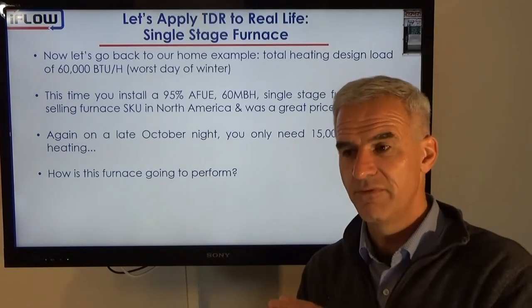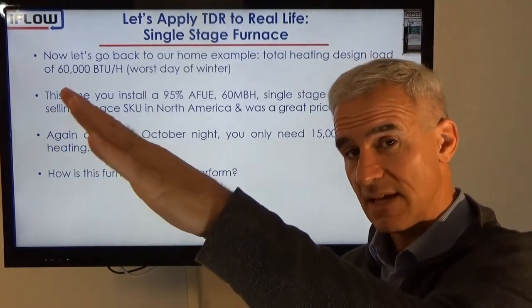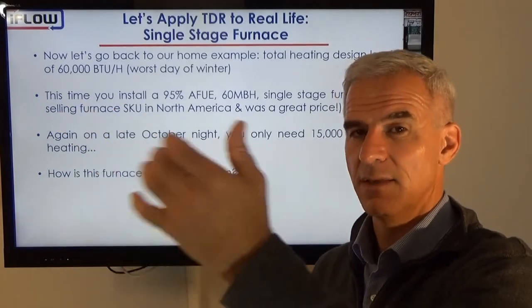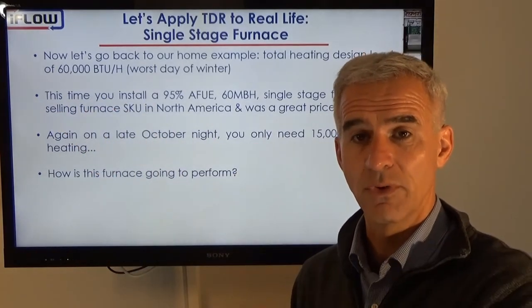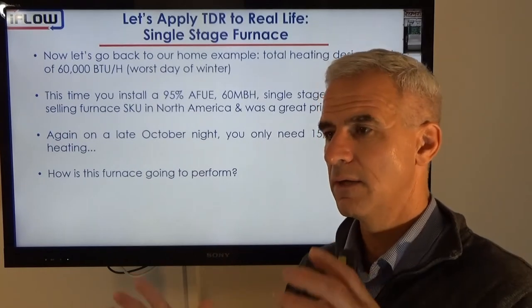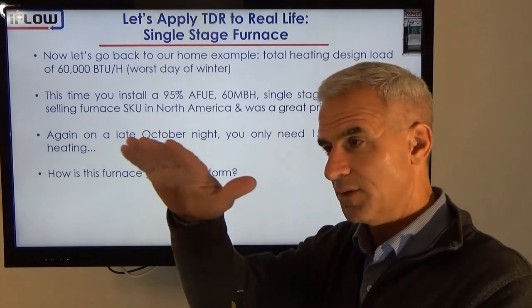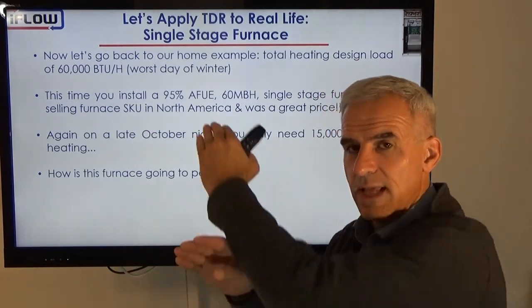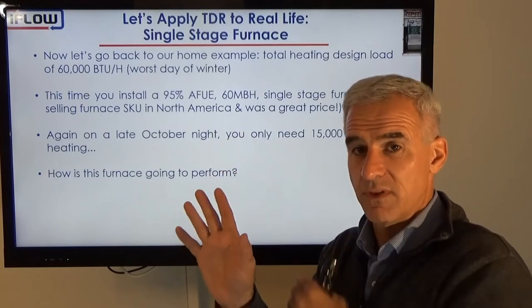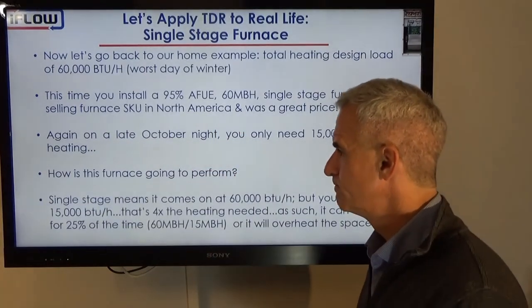So I'm going to be on for 5 minutes, delivering 60,000 BTUs worth in that 5 minutes, and then I'm going to shut down. If I don't, I'm going to overheat the space because I'm delivering too many BTUs in that shorter period. So then I'm going to stop for 15, let the room cool down again, and then I'm going to come on again and deliver the 60,000 BTUs worth for the 5 minutes, and then shut down. I'm going to do that cycle 3 times.